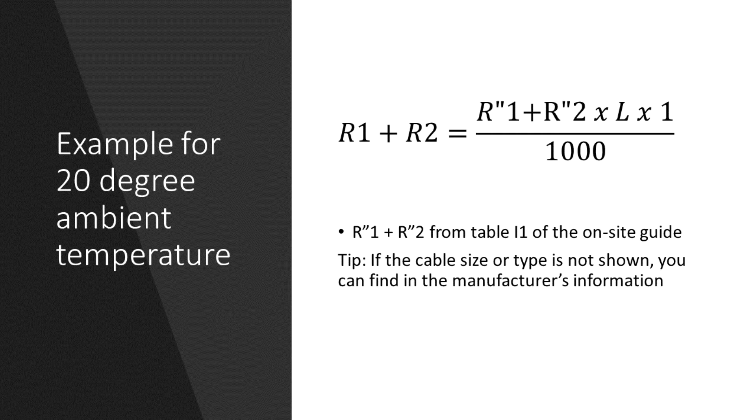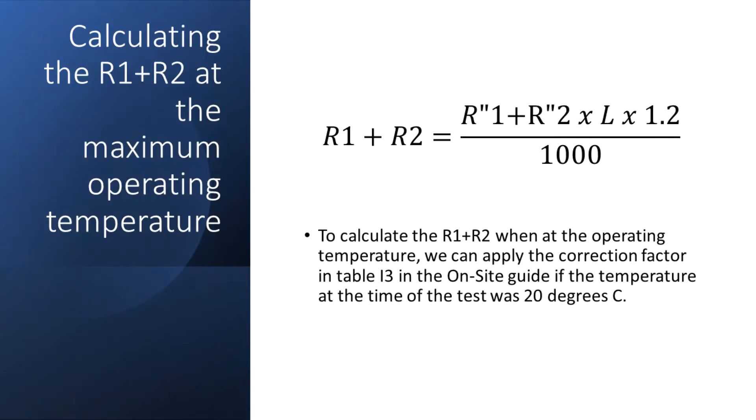Then to calculate the R1 plus R2 at the operating temperature, we can use the correction factor on the next page on table I3 which gives us a factor of 1.2 which will basically add 20 percent.